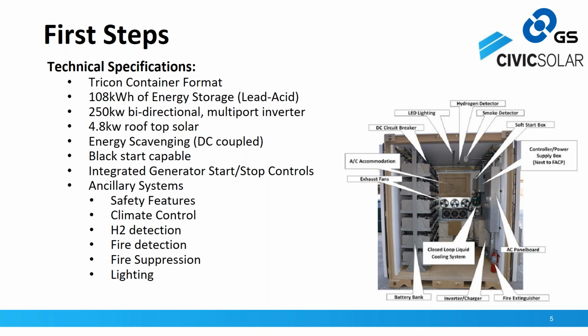It was also black start capable. We talked to some of the leaders of the military operations, and they said they wanted to put this device on the ground first, immediately start it up without any connection to generator or grid, and start delivering power to critical loads. Then at a later time they could bring in generators to support the device, bring in solar to support the device, and bring in additional critical loads as those assets hit the ground.